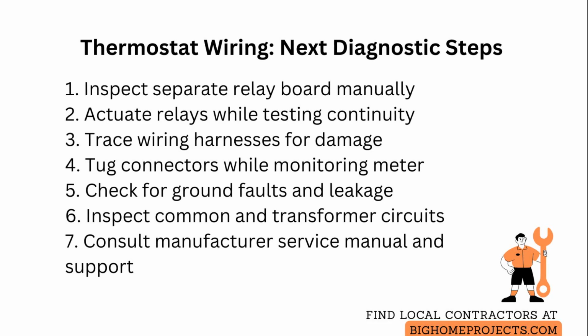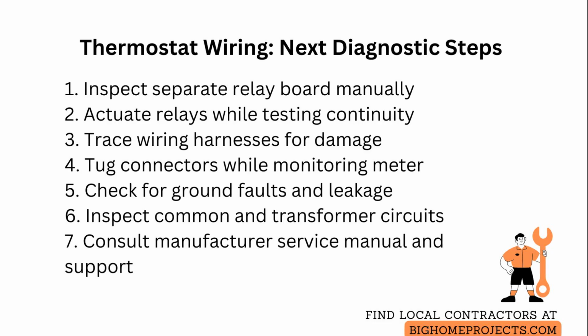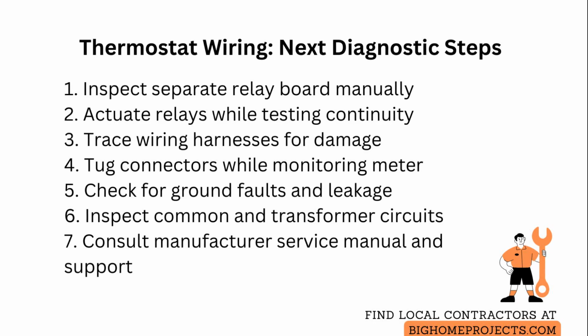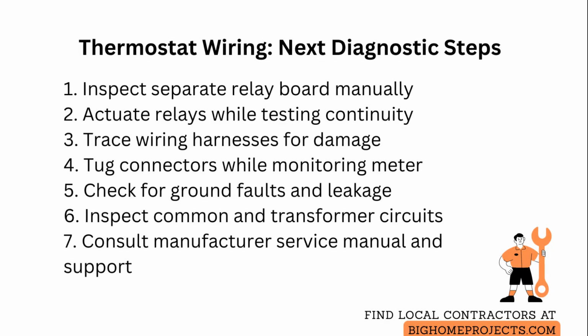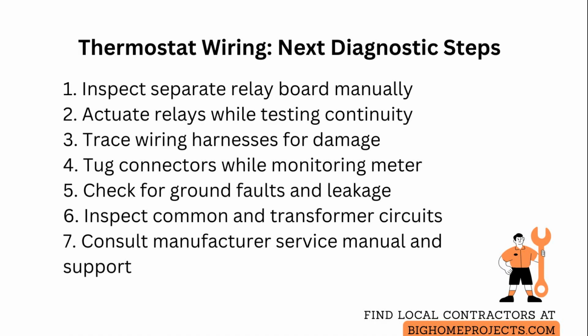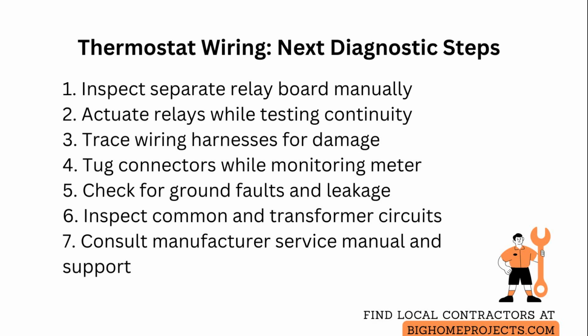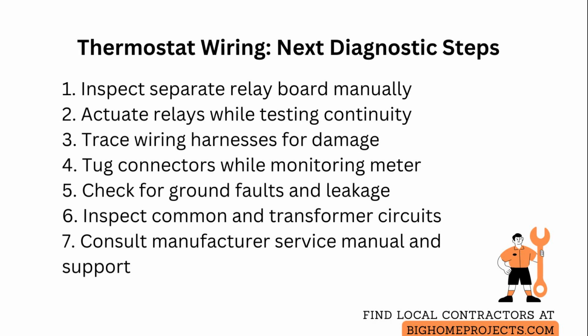Use the manufacturer's service manual to follow recommended diagnostic sequences for ancillary modules such as condensate overflow switches, float switches, and safety interlocks that may open a control circuit without tripping obvious alarms. If diagnostics still fail, document your findings with photos and exact meter readings, then consult manufacturer technical support for firmware quirks or known failure modes that are not in the public manual.